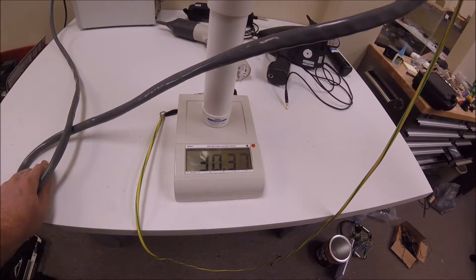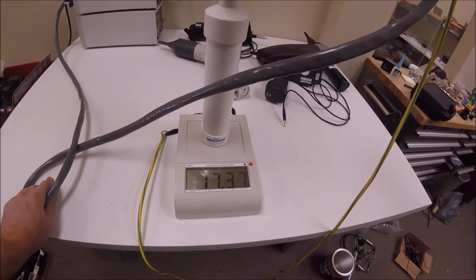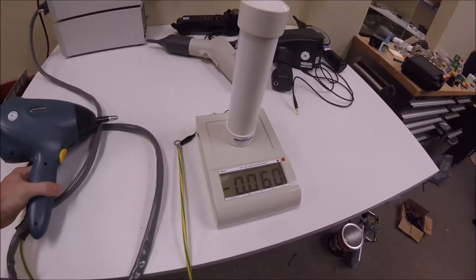There is also a chart on the bottom part of the screen that calculates the 5% deviation allowed on the four levels of IEC. After releasing the trigger, you'll note the meter wind down with a dissipation of voltage.